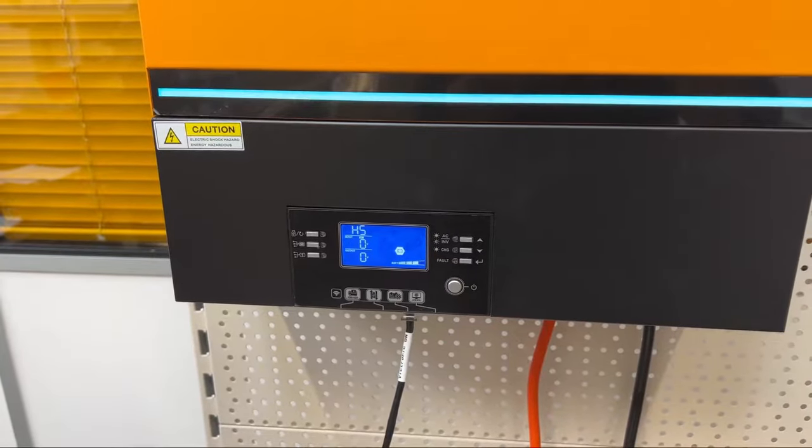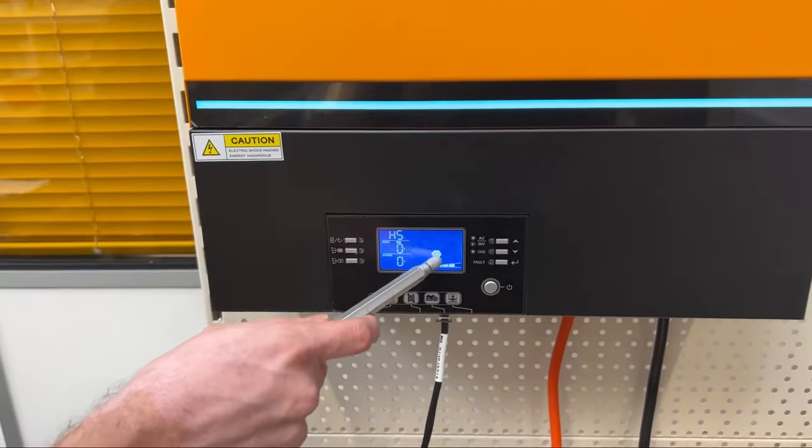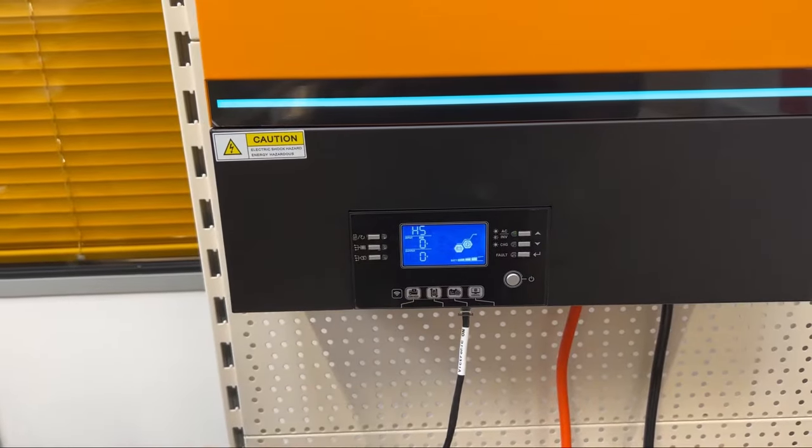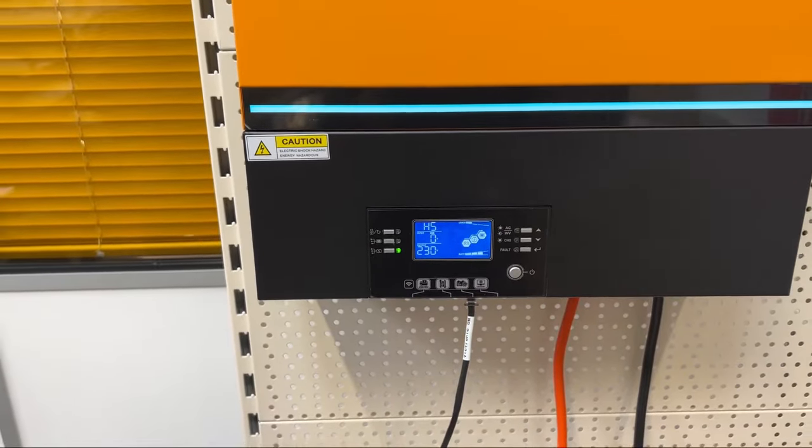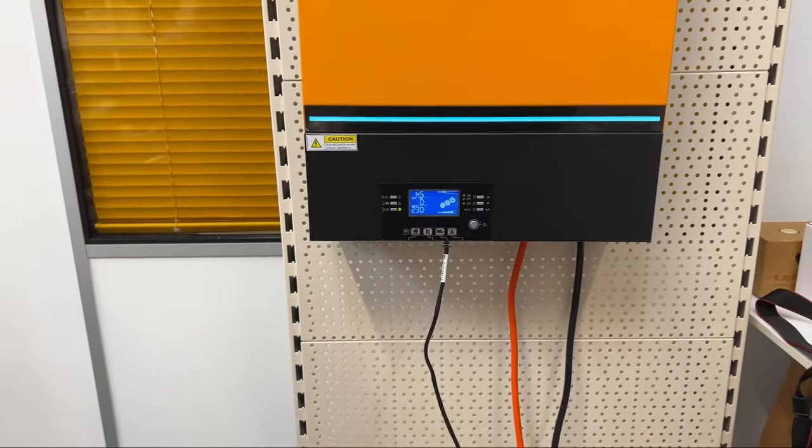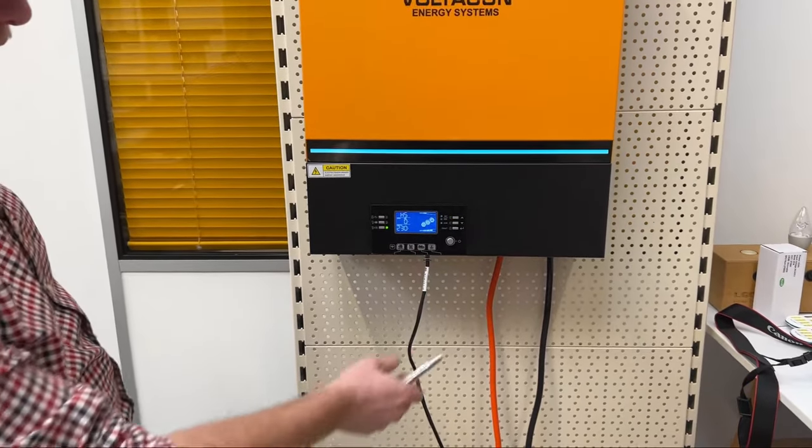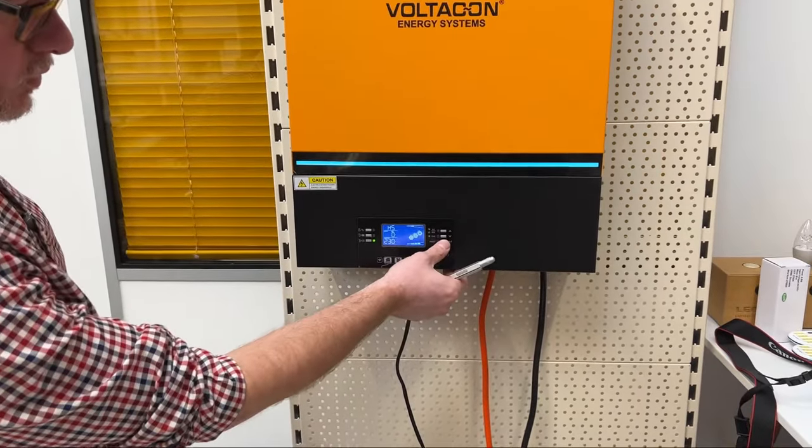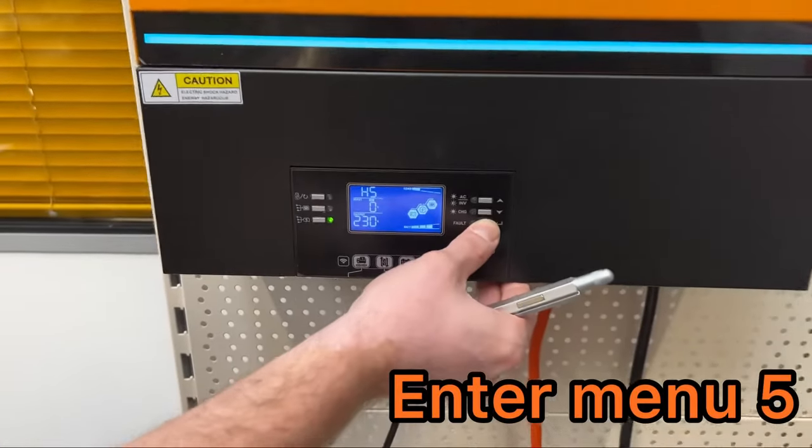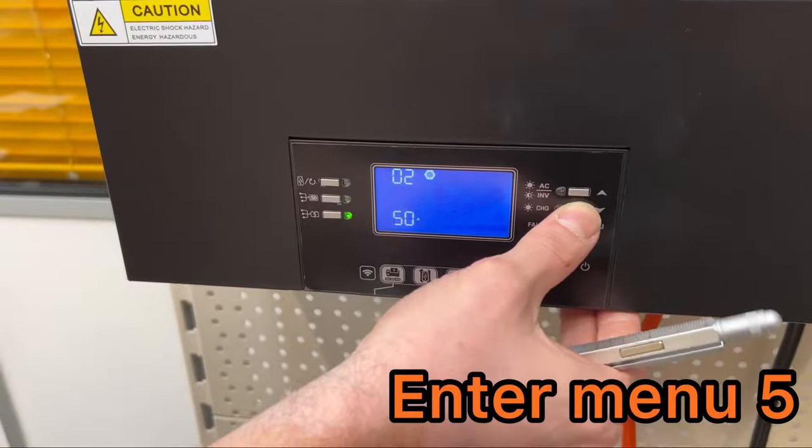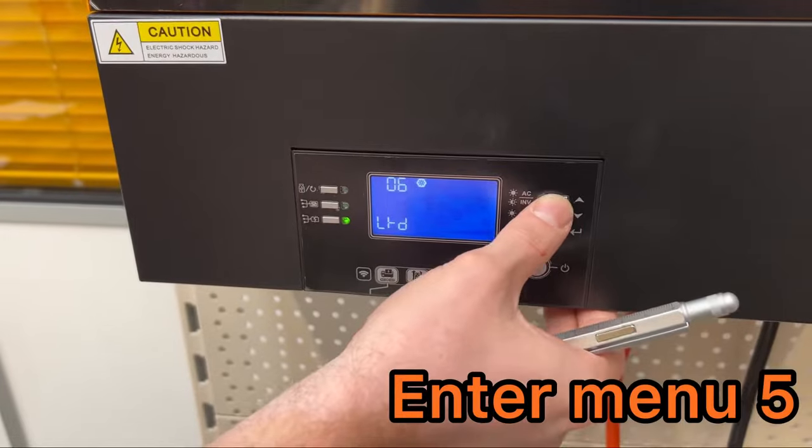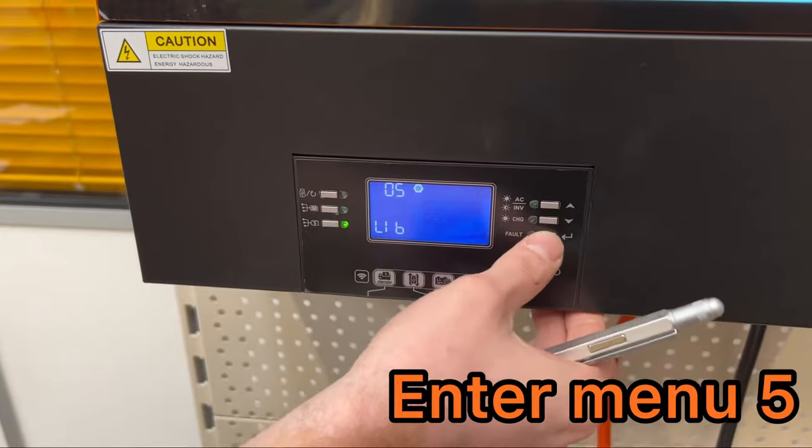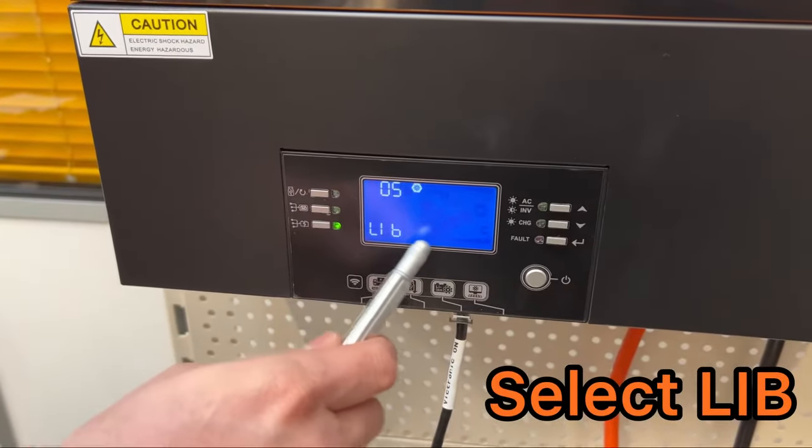When the battery icon is flashing it means that the BMS communicates with the inverter. In order to do that you have to enter menu 5 and select the protocol LIB.